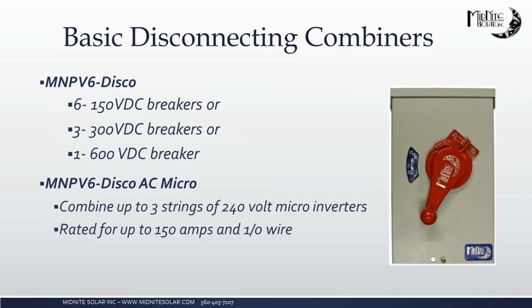So if you had an older grid tie inverter and you needed a disconnect that would do the DC and AC all in one, you could do that. The 300 volt model, which we call the -250, will take up to 3 of the 300 volt DC breakers, and those go up to, I believe, 50 amps a piece, and you could get 3 of them in there. That is a different model.